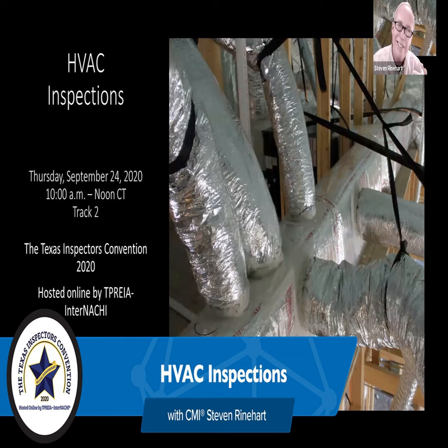But the wires, are you going to read the wire sizes and then open up the cover and look at the maximum wattage of all the elements running at one time? That's excluded somewhat in the standards. Here, we're not really talking size, we're talking condition. Are they beat up, cut, burned, look like they've been overheated? That's what we're looking for there.